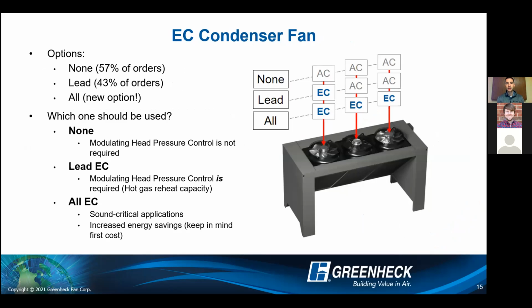Sticking with the condensing section, I want to talk a little bit about EC condenser fans. A number of different options that you have on our products. First one is going to be obviously selecting none, which means all AC condensing fan motors. You can select lead, which about 43% of our orders right now are selected with, which means that lead condenser fan will be the EC motor. We'll modulate that one accordingly, and then we'll have AC motors staged after that. And then we do have a new option on this type of equipment where it is an all EC motor configuration, which means obviously all condensing fans will utilize those EC motors.